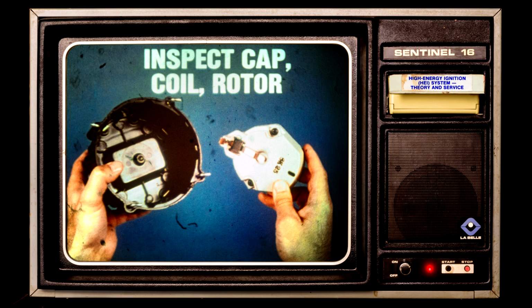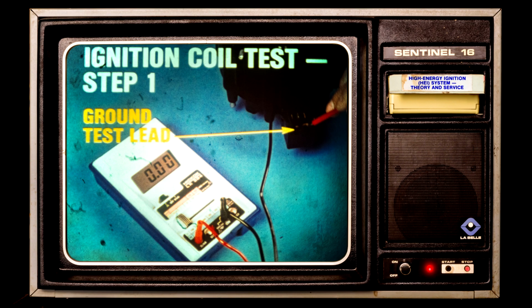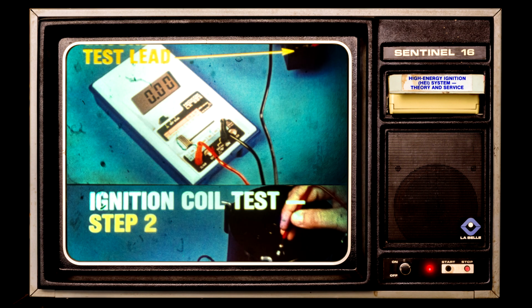So, at this point, remove the cap and inspect the cap and rotor. Replace them if you find any damage. Here's how you can test the coil. Connect an ohm meter as shown here and take a reading. If this reading is more than 5 ohms, replace the coil. If it's less than 5 ohms, proceed to step 2.